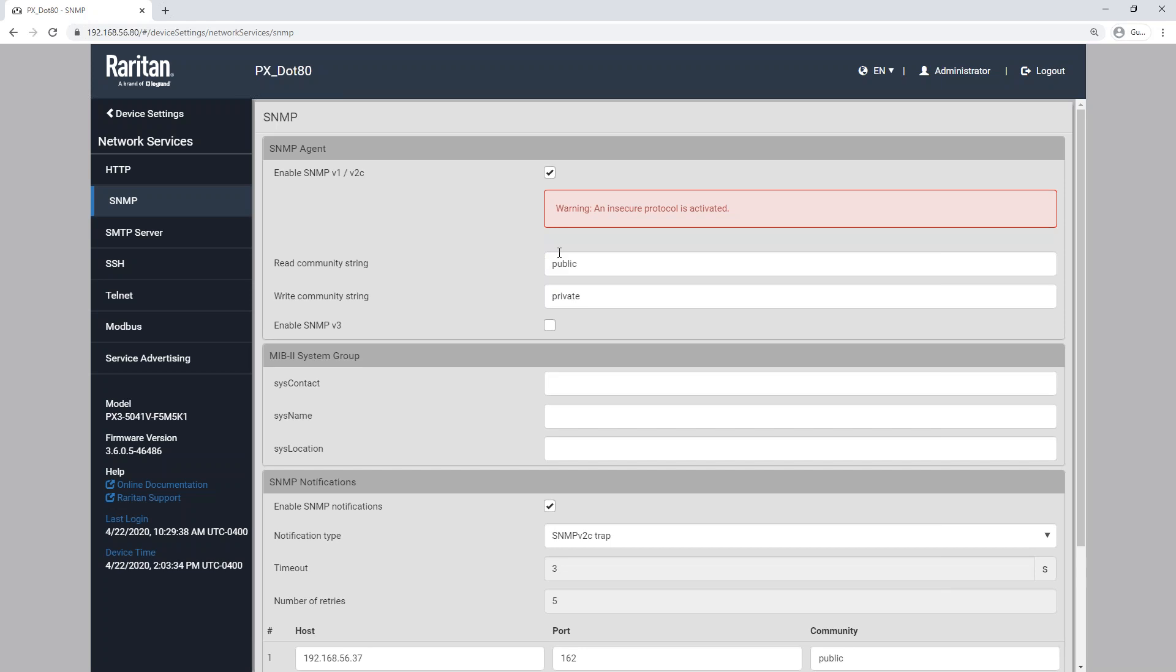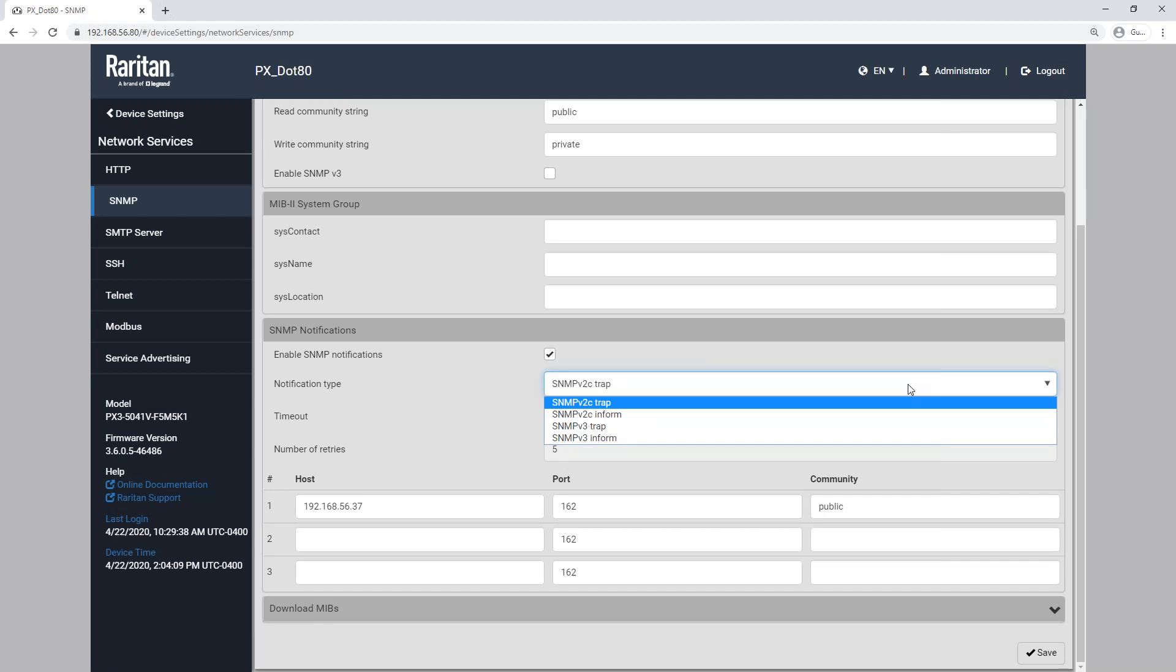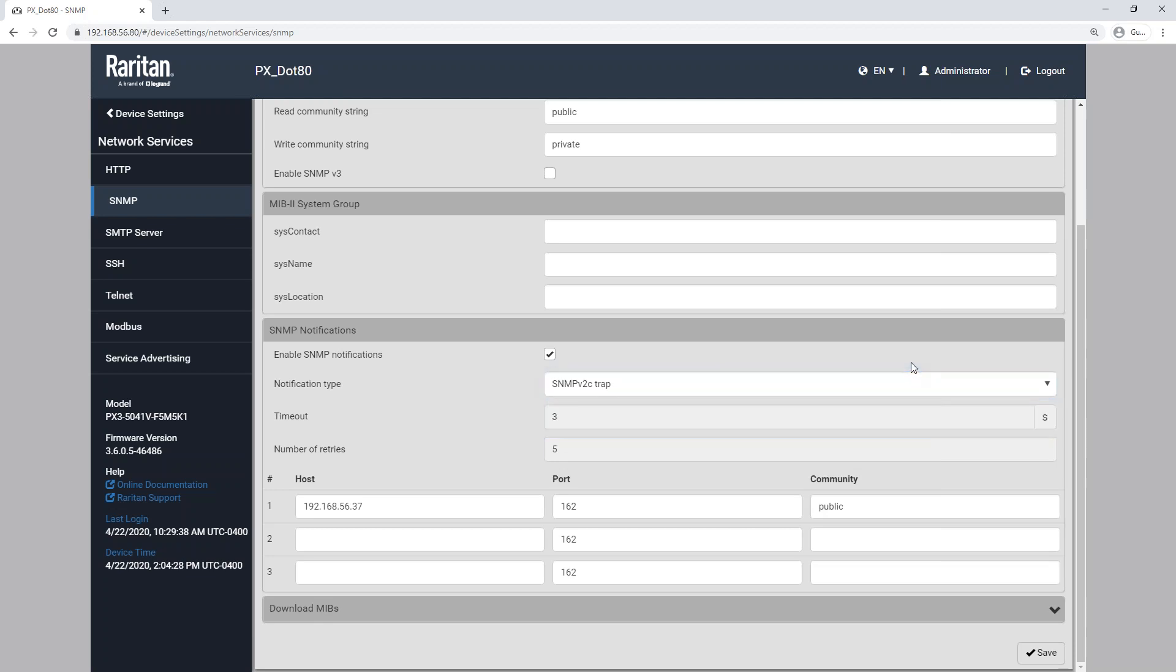These are the settings that allow the PDU to be polled by your SNMP manager. And that SNMP manager in our case is PowerIQ. And it's really only polling the PDU every five minutes or so, depending on how you have it configured. So if a critical alert were to pop up, we want to make sure that that gets sent to PowerIQ immediately, so that we're notified. So down at the bottom here, we have SNMP notifications. And by default, these are disabled. So this checkbox is not filled in. So we want to go ahead and select that. And then you'll see notification type. So there are a few different options to pick here. We have V2C traps, V2C informs, and then V3 traps and informs. Inform message is the same thing as an SNMP trap. However, it allows the SNMP manager to send the acknowledgement back to the Raritan PDU so that we are aware that the SNMP manager actually received it and didn't just throw the trap away and drop it off.